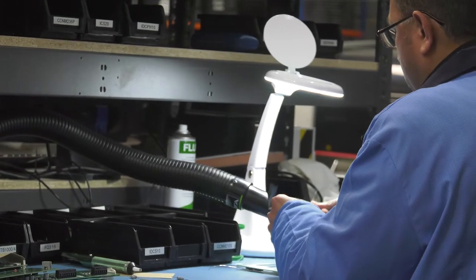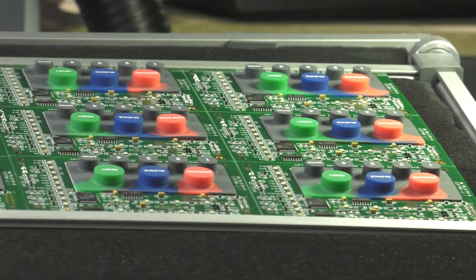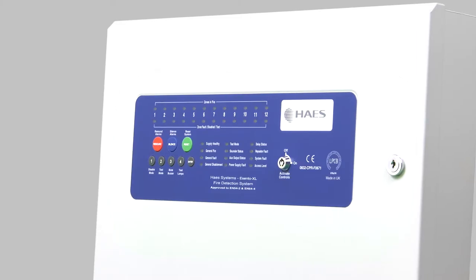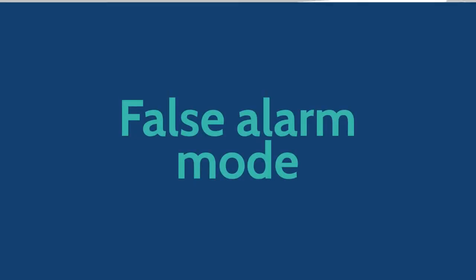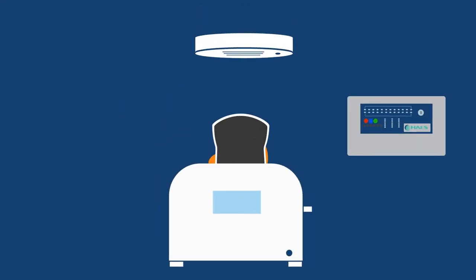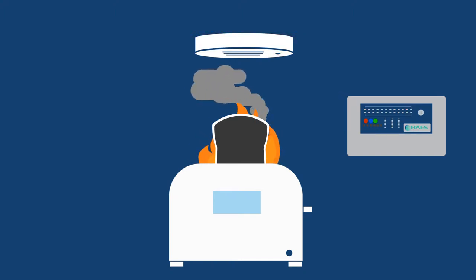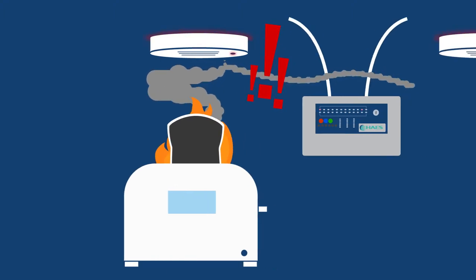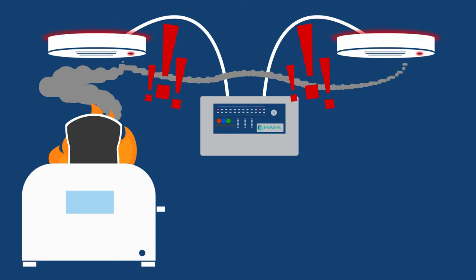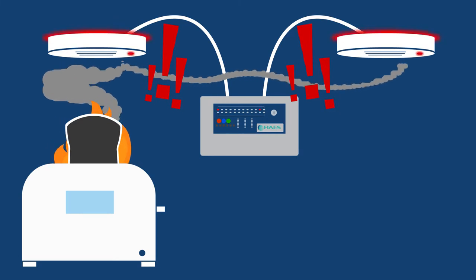The programming capability of this panel enables numerous configurations. Here are two examples. False alarm mode: if someone burns their toast and smoke is detected, the system will recheck a second time after a short delay and will only sound the alarms if there is still smoke detected, or the system will trigger the alarm if a second detector detects smoke, greatly reducing nuisance false alarms.